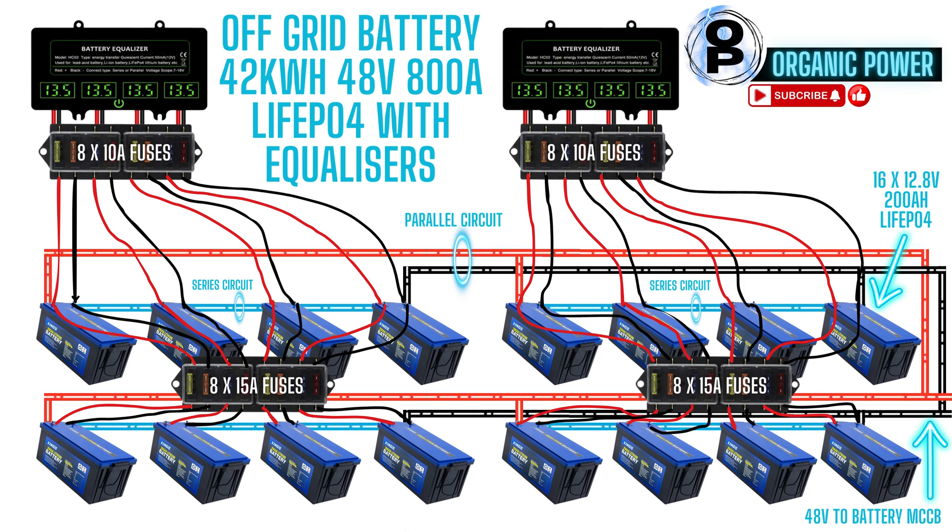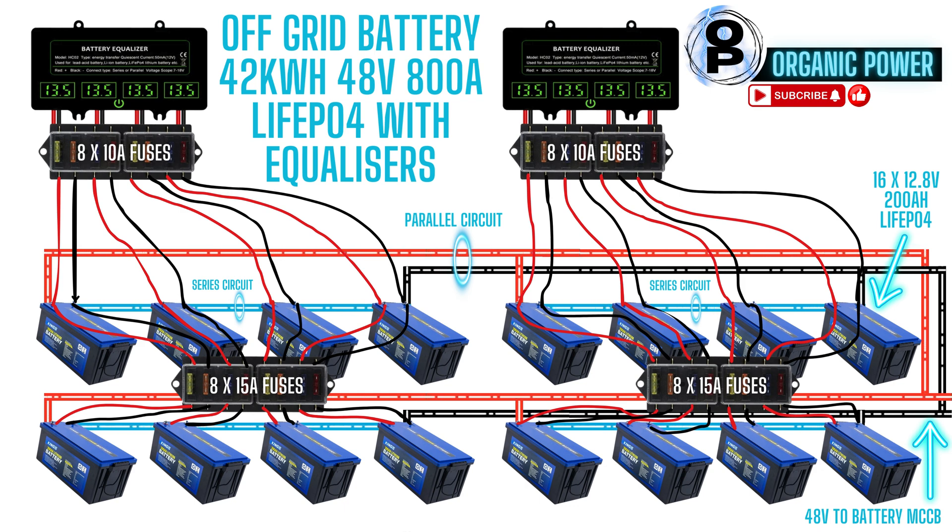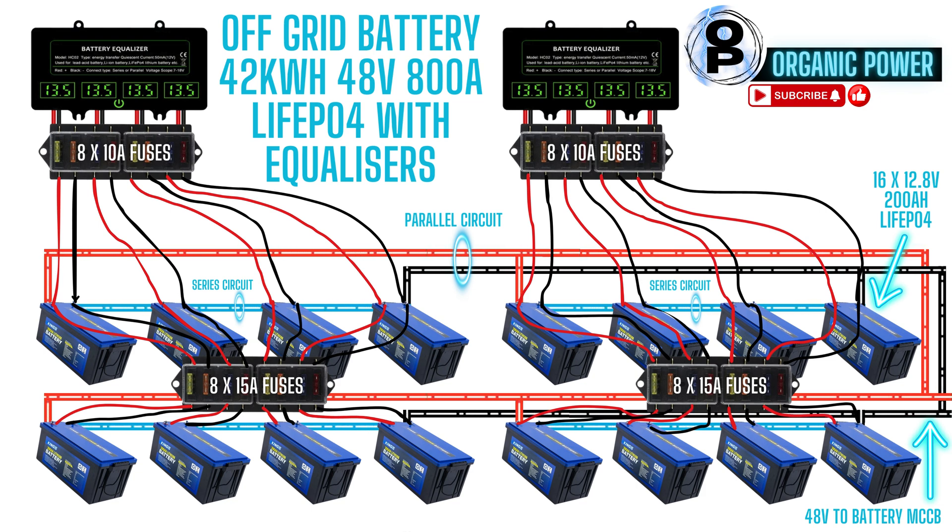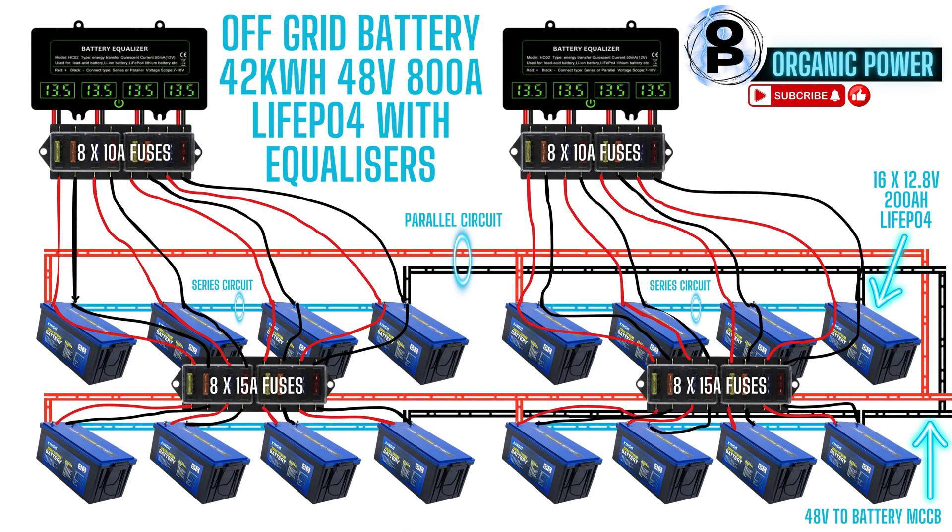55 volts is my bulk absorption mode, and 54.2 is my float. Once the four series circuits of the batteries are connected in parallel, the voltage will remain the same at 48 volts, but the current will quadruple.